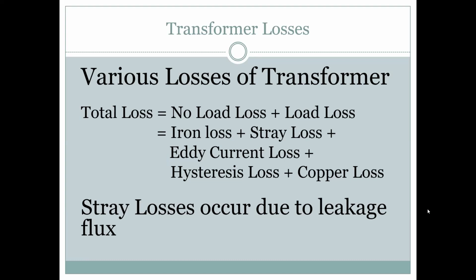Then copper loss. In the winding, that is the copper loss, the I squared R loss that we call. That is because of current passing through the copper windings, and this gives you the copper loss. Stray losses are due to the leakage of flux. Whenever the flux is not connecting to the other secondary winding, it will be wastage basically. So that is the stray losses. Next.